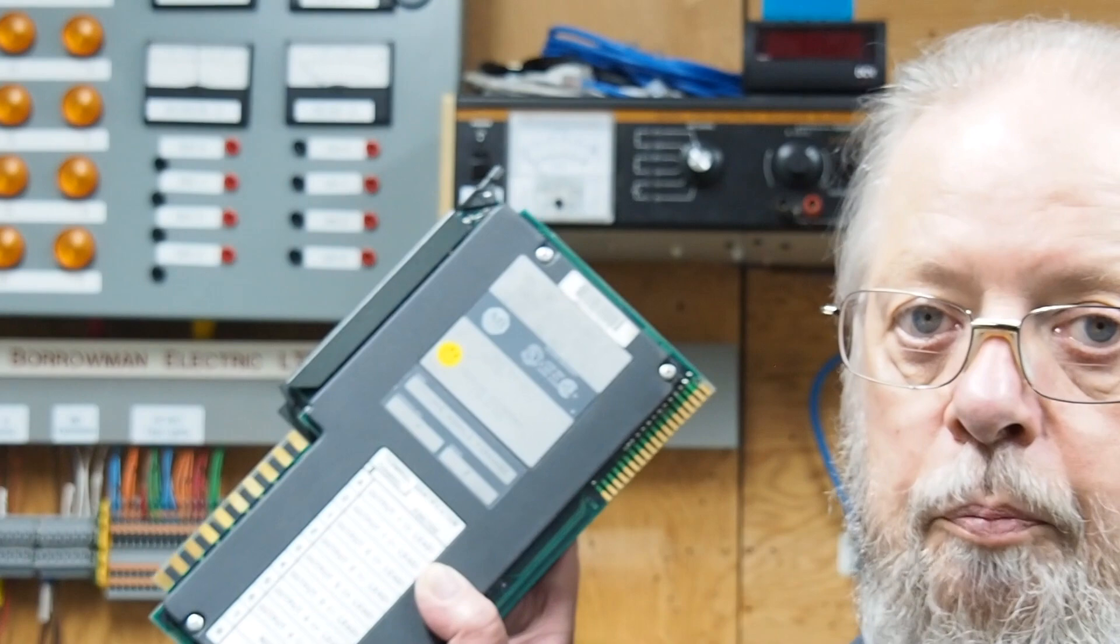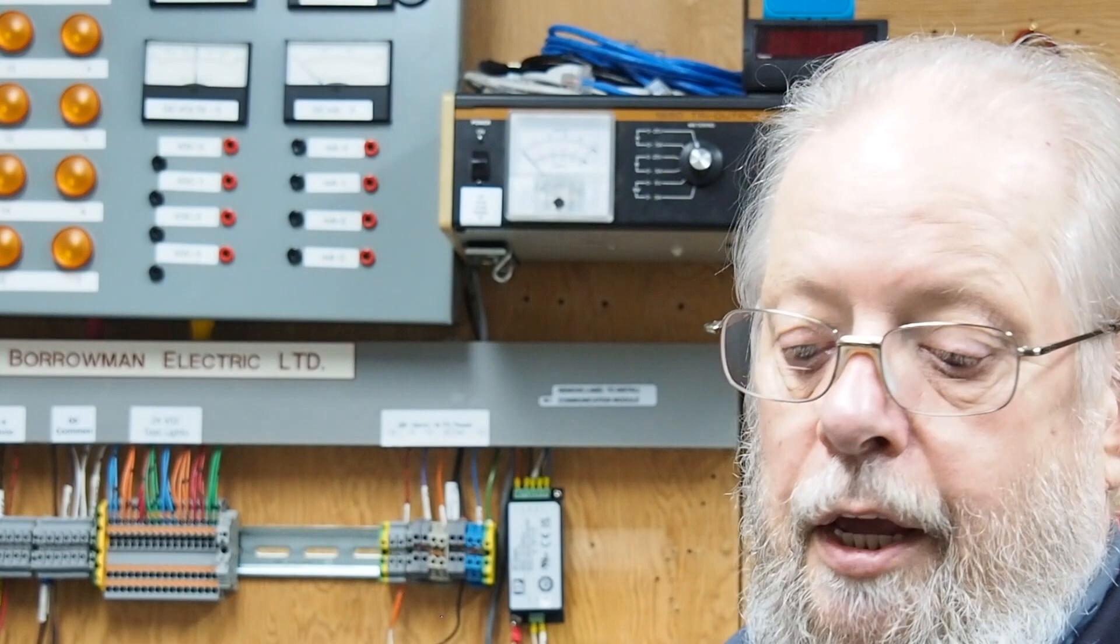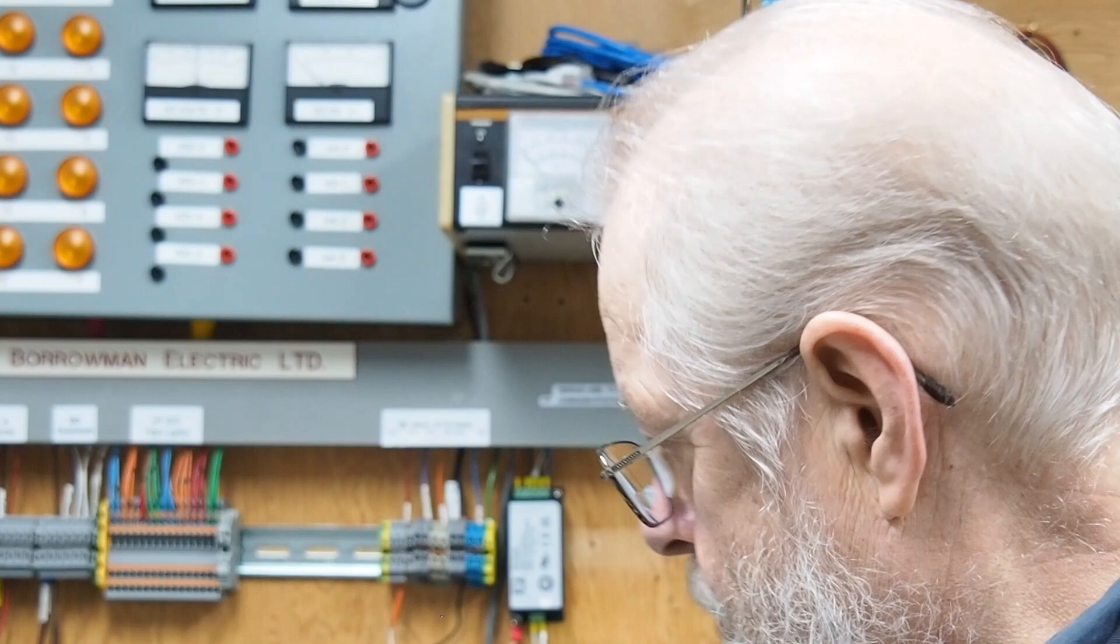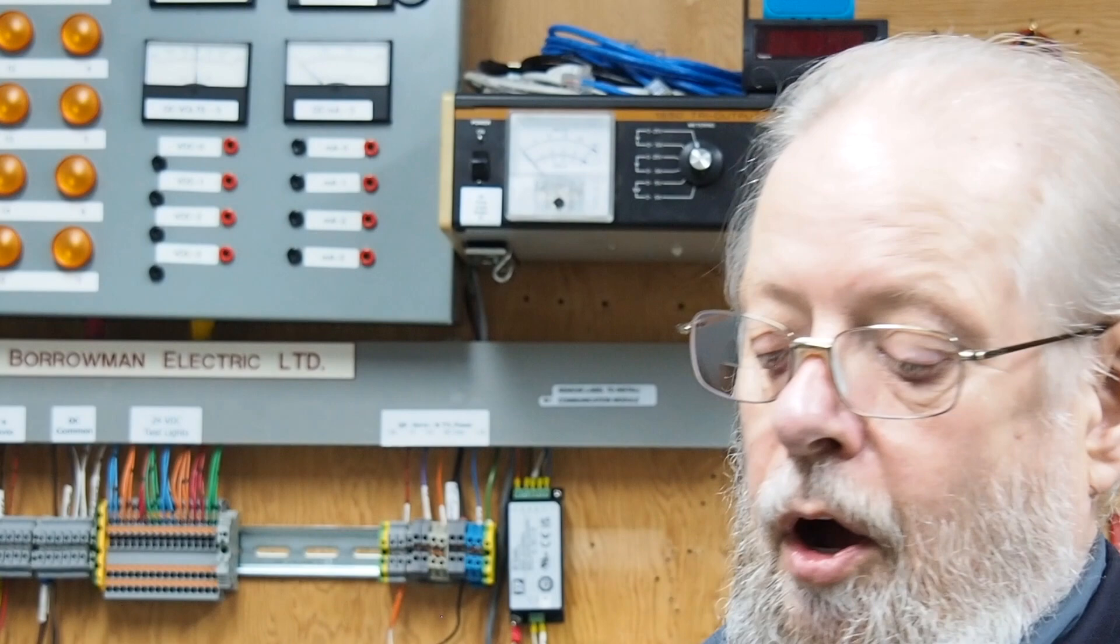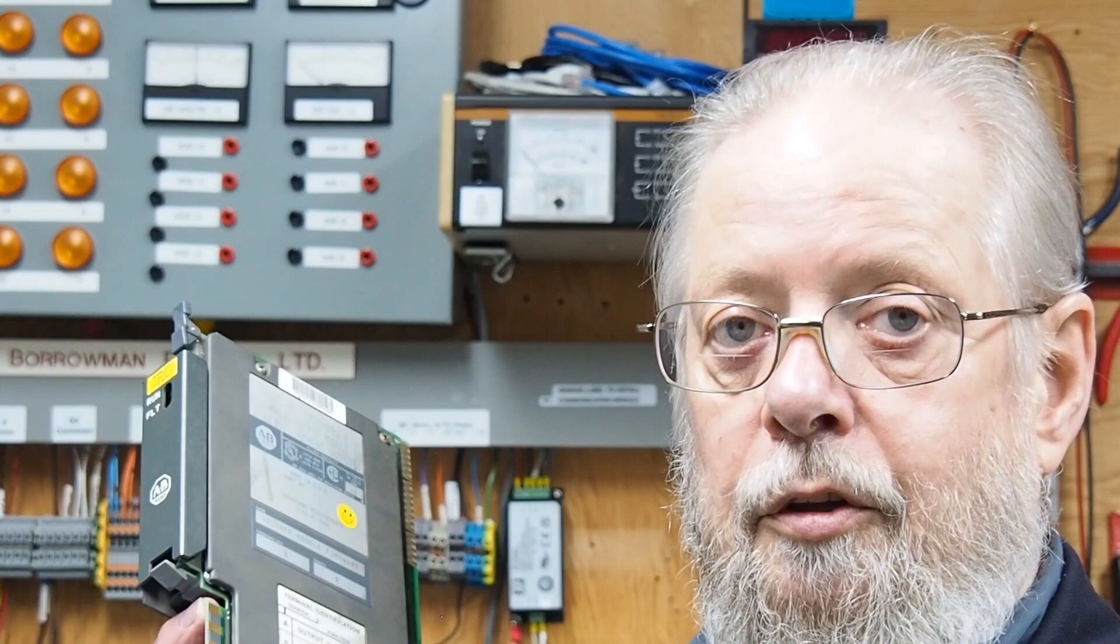To test these, because it's a 16-channel single-ended input, what I've had to set up for voltage, I'm using an OFE1 analog output, and these do voltage only, and they're four channels. So I have one wiring arm made up for voltage, and each of the four output channels does four input channels. It's pretty straightforward and simple. On the current, same thing, on the OFE2, which is a four-channel analog output card.